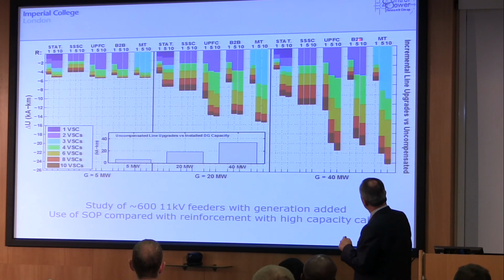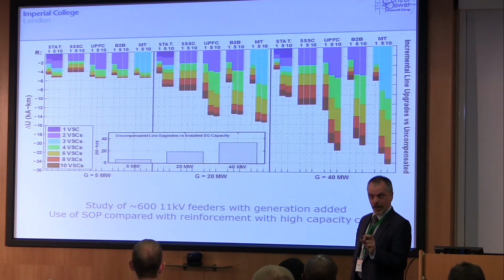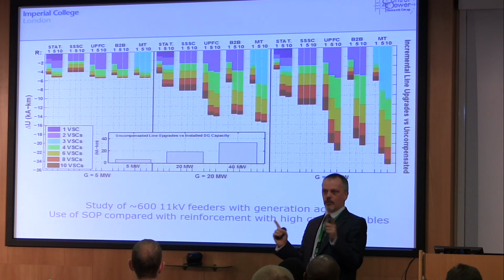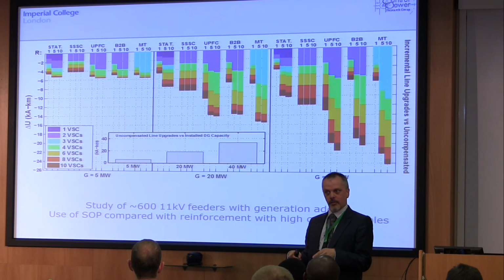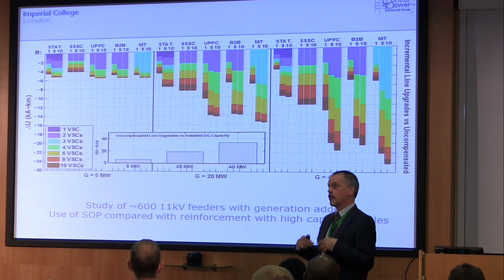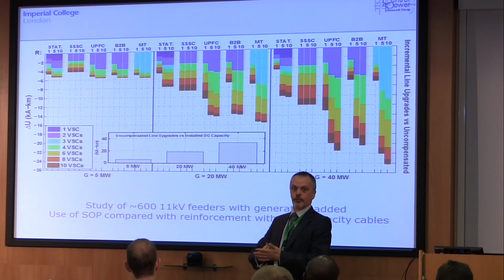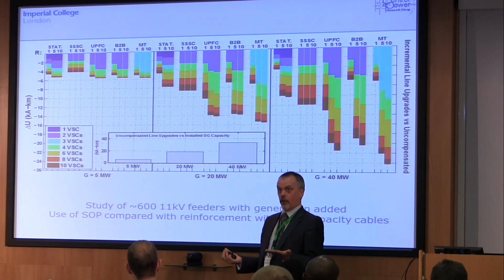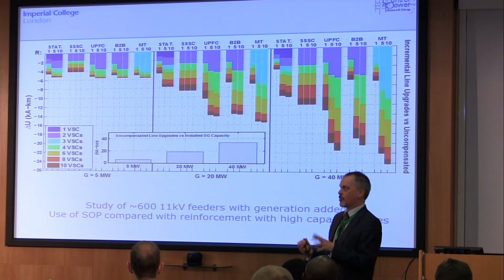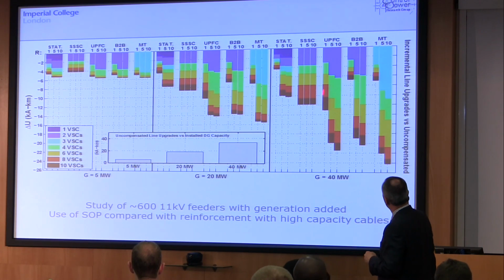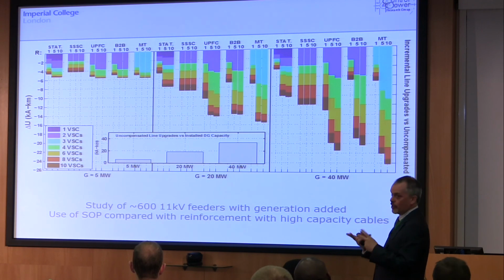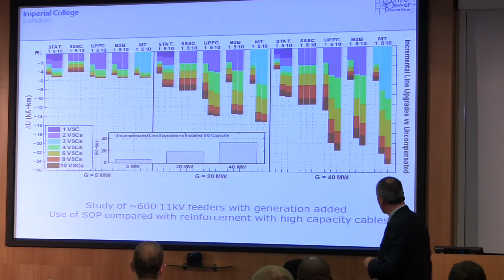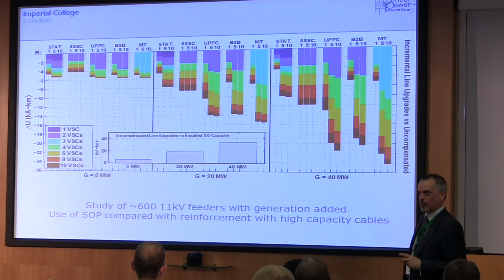But there are problems here. The back-to-back converters are attractive because they can shift power between two feeders, but shut down in the event of a fault and block fault current. So they operate to close the feeders for normal operation, but look like they're open under fault conditions, which means the protection system doesn't have to be redesigned. The UPFC, because it's partially rated, can't block the fault current. So although this might look a bit better, it might not be the one that flies.